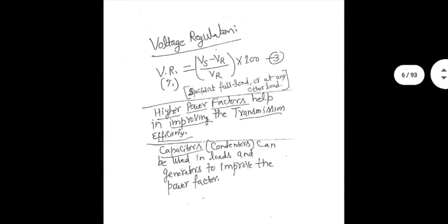Voltage regulation is another thing that will come again and again in this course. It is the sending end voltage minus receiving end voltage, only magnitudes, don't worry about phase, divided by receiving end voltage and the entire thing multiplied by 100. Ideally, you should have 0% voltage regulation. That means sending end voltage and receiving end voltages should be the same. It's not possible because of losses in the line. So let's say 5 to 10% value of voltage regulation is generally acceptable. Anything more than 10% will be objectionable. You have to do something about it.